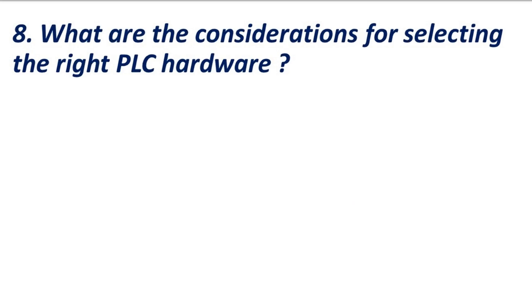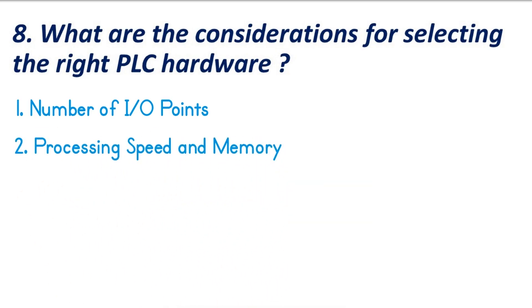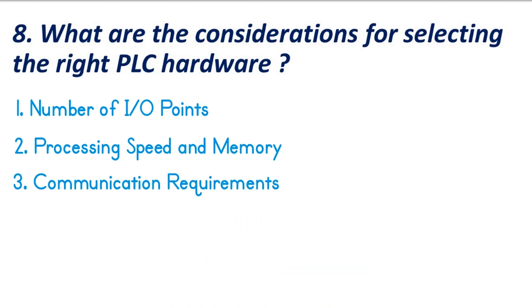What are the key considerations while selecting a PLC? The first consideration is number of I/O points — determine the total number and types of input-output devices needed and ensure the PLC has sufficient I/O capacity. Second is processing speed and memory — select a PLC with adequate processing speed for real-time operations and enough memory according to your program's complexity. Third is communication requirements — ensure the PLC supports necessary communication protocols for integration with other devices like SCADA and sensors.